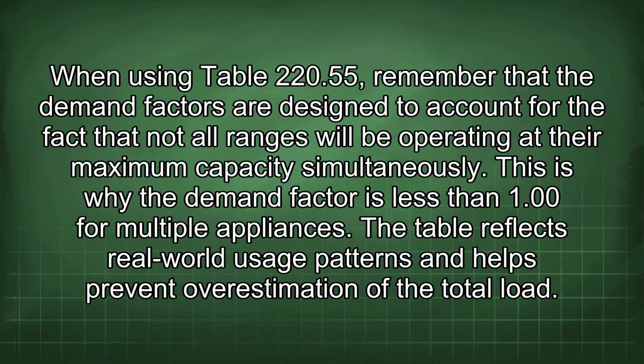When using Table 220.55, remember that the demand factors are designed to account for the fact that not all ranges will be operating at their maximum capacity simultaneously. This is why the demand factor is less than 1.0 for multiple appliances. The table reflects real-world usage patterns and helps prevent overestimation of the total load.